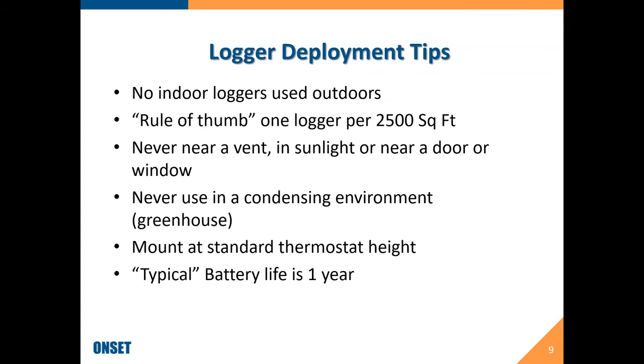When you deploy a logger, you never want to deploy it near a vent where it would be blown on with cooling or heating air. You don't want to put it in a place where the sun hits it. Otherwise, you'll get defective readings because of the heating of the sun, or near a door or window. If somebody opens a window and you're trying to get a temperature and relative humidity profile, they'll throw everything off. Never use indoor loggers in a condensing environment. A condensing environment would be like a greenhouse. A lot of people think that even though a greenhouse is indoors, it is really an outdoor environment.